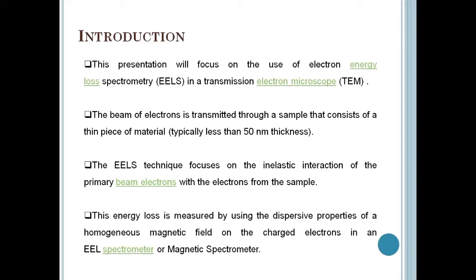Interaction of the beam with the sample enables the operator to learn about the sample, such as chemical elements present, stoichiometry, energy levels, electronic structure, and more. The EELS technique focuses on the inelastic interaction of the primary electrons with the electrons from the sample. The energy loss of the primary electrons commonly used in EELS is in the range of 0 eV to 3 keV. This energy loss is measured using the dispersive properties of a homogeneous magnetic field on the charged electrons in an electron energy loss spectrometer, or magnetic spectrometer.